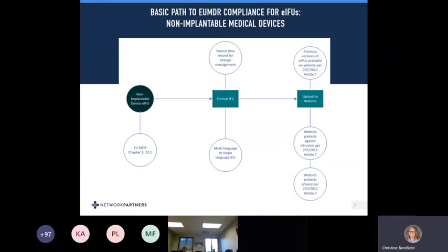There's also some basic requirements for the website. Any website containing instructions for use shall fulfill the requirements set out in points B, E, and G of paragraph 2 of Article 7 of Regulation EU number 207/2012. B, it shall be protected against hardware and software intrusion. E, it shall fulfill the requirements of Directive 95/46 EC, since superseded by General Data Protection Regulation, the GDPR. And G, all previous versions of the instruction for use issued in electronic form and their date of publication shall be available on the website.